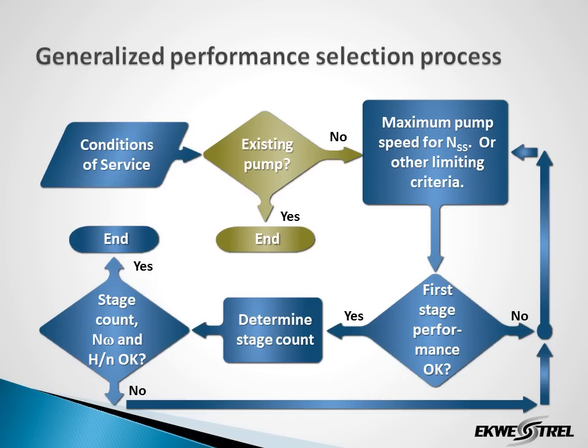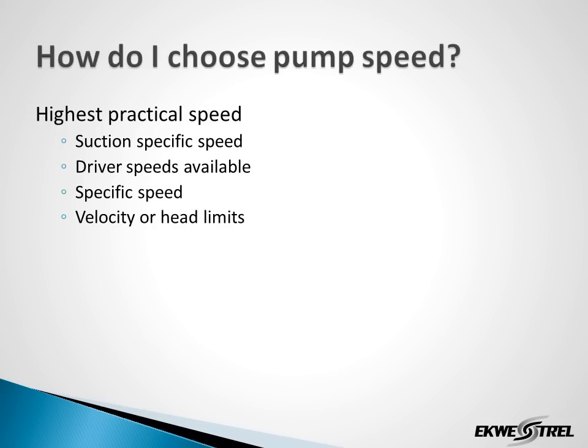Once the conditions of service are established, the first choice would be an existing pump design that can meet all of the performance requirements. Specified industrial pumps, even when they are existing designs, may have some modifications or special materials of construction, and are often manufactured to order. If there is no existing pump design that meets the conditions of service, then the process of finding one starts with selecting the pump speed. The highest practical speed will result in the smallest pump size and most economical selection. Issues related to the selected speed are suction-specific speed, driver speeds available, specific speed, and any velocity or head limitations.